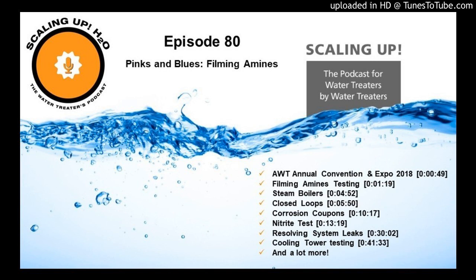If you're trying to get exactly that of makeup water, you're probably going to waste a lot of water, and that's not really necessary. So we decided we got to a certain point, we were good with that, and then we started adding the Filming Amine. Now, the Filming Amine manufacturers recommend that you half the dose, and then 1 month later, you come back and add the remaining half a dose. So you have the entire dose in the system, but over a 1 month period.